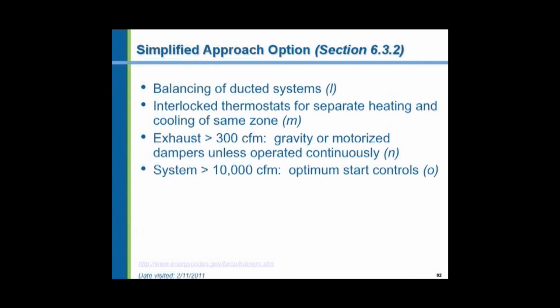Again, if you have thermostats in different zones, the zones might touch one another. You cannot have one zone heating at the same time as the other one's cooling if they're adjacent to each other. And if you have exhaust systems greater than 300 CFM, they have to have dampers on them, gravity dampers or motorized dampers that seal tightly, unless the systems operate all the time. And if the system is large enough to be 10,000 CFM or larger, it has to have what's called an optimum start control. And that's basically a thermostat system that learns over a period of time the thermal flywheel performance of the building and starts the furnace or the air conditioning system appropriately in advance so that it's up to temperature or down to temperature by the time the occupants come at 8 o'clock in the morning.